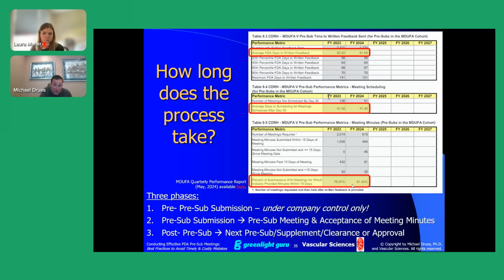So if you don't talk about usability testing in your original pre-sub, you cannot go to the FDA with a pre-sub supplement on usability testing. However, nowhere in the guidance or regulation does it say anything about the level of detail in that pre-sub description. So if I simply mention that I'm planning on doing usability testing, details TBD, and don't say anything else, then that allows me technically to go back to the FDA later with a pre-sub supplement with nauseating detail on usability testing or biocomp or electrical safety or whatever it is, as long as you mention it in there.